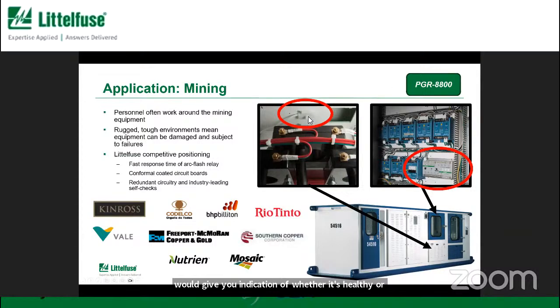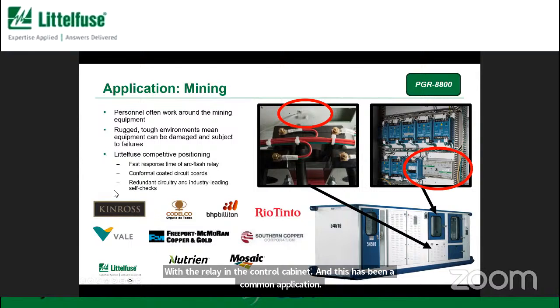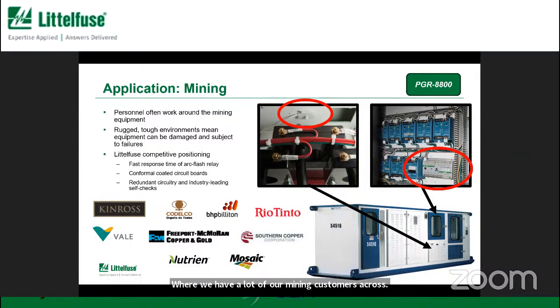This is another example of a point sensor installed above a current transformer compartment in mining switchgear. This is an underground mining substation that's very ruggedly built, and again, another good place for arc flash protection with the relay in the control cabinet. This has been a common application where we have a lot of our mining customers across South America, North America, Australia, using our arc flash relays across their site.